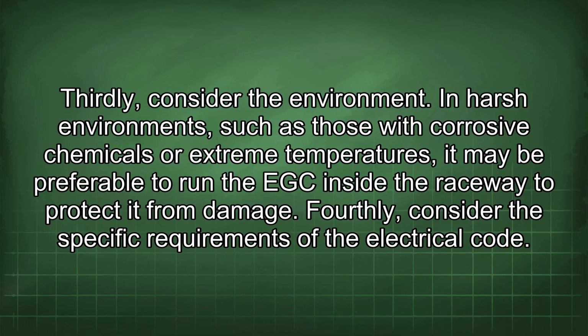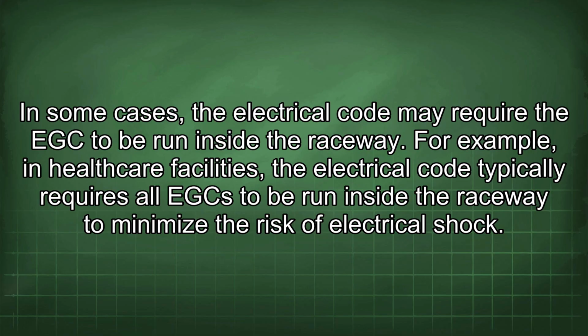Fourthly, consider the specific requirements of the electrical code. In some cases, the electrical code may require the EGC to be run inside the raceway. For example, in healthcare facilities, the electrical code typically requires all EGCs to be run inside the raceway to minimize the risk of electrical shock.